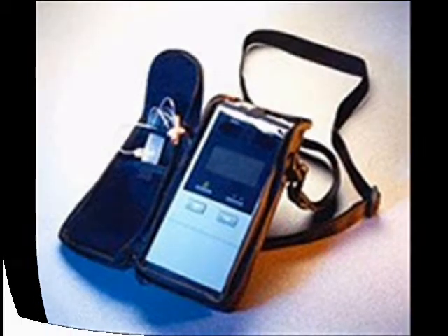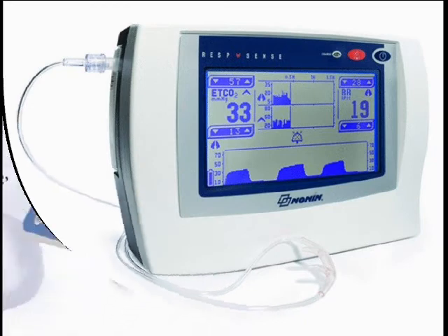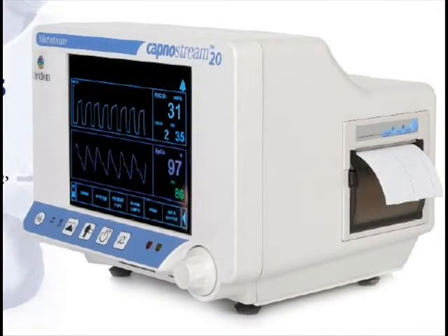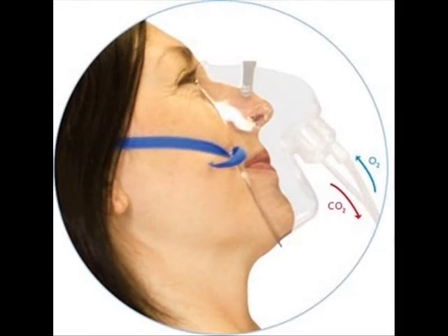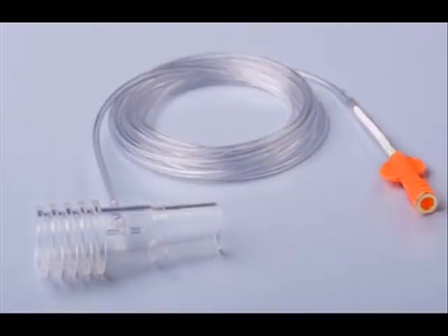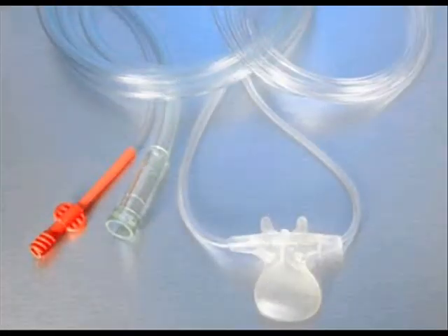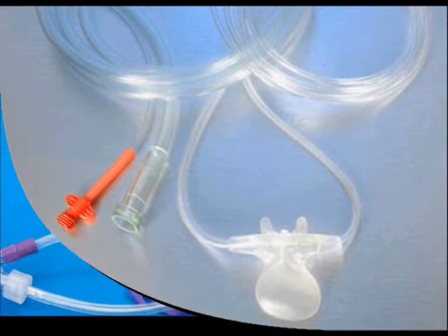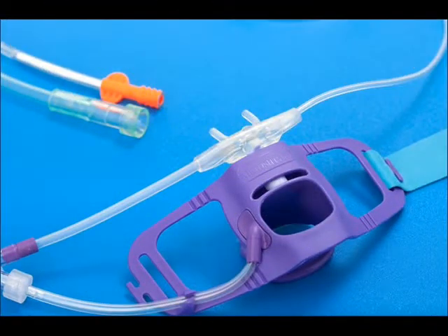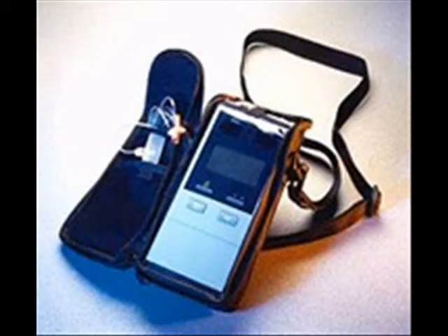With the CapnOxygen mask, you are able to securely attach it via a Luer lock right here on the mask. You're providing 6 liters or more of oxygen to your patient, and the entire time you're getting an excellent CO2 waveform. The CapnOxygen mask is a great provider of CO2 monitoring and oxygen for MAC or monitored anesthesia cases.